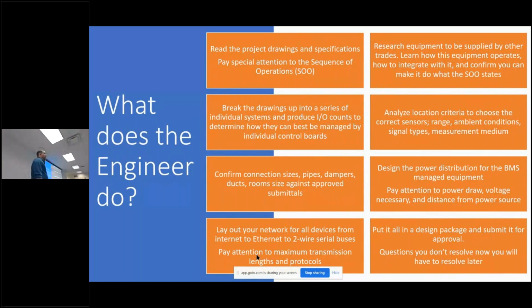Now you have to worry about things like, I'm going to put my transformer in some location in a building, and I'm going to use it to power all of my devices and controllers. But how far can you take that power before you have voltage drop across your lines? How much capacity do you have before you run out, or maybe you have too much capacity running through a line and you have to increase the size of that line, duplicate it, or add additional power supplies throughout the building. Now you have to figure out where you're going to get that power. So reading the drawings helps you figure out how you're going to solve these problems as you go through creating your design.